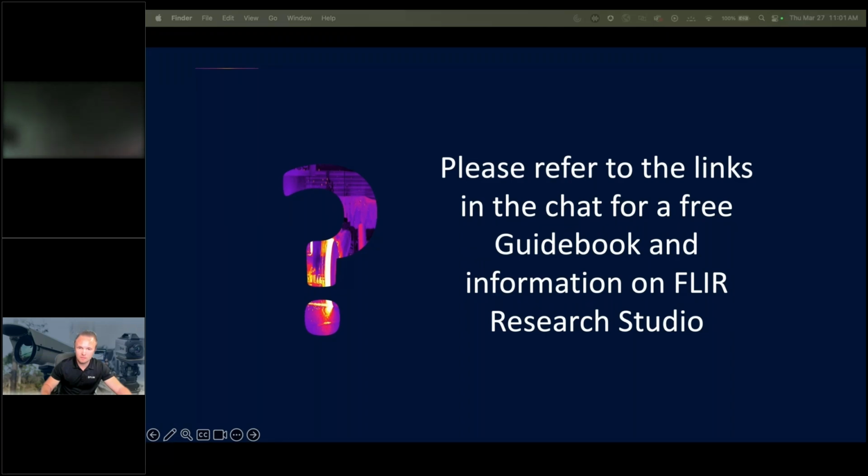So as the user, it's your responsibility to make sure you have a good emissivity and reflected temperature entered. There are lots of questions about emissivity, so that tells us that maybe a future webinar should be emissivity centric. Yeah, and we'll send some information out in the package that everyone gets on this, showing how the emissivity calculator works.